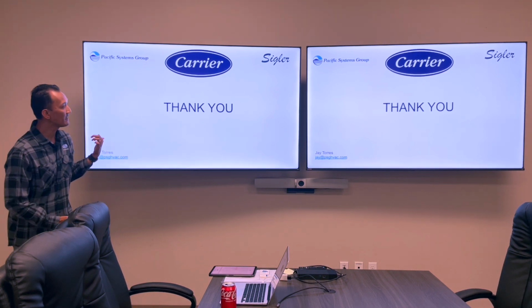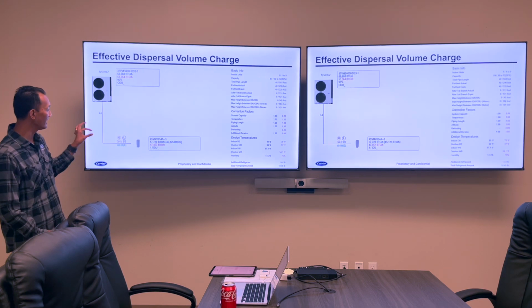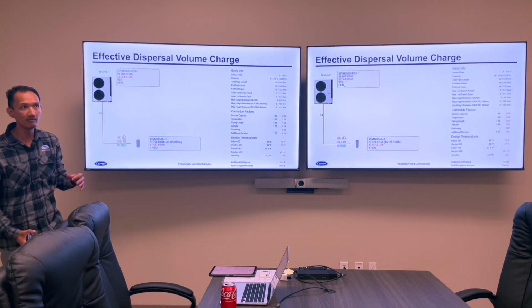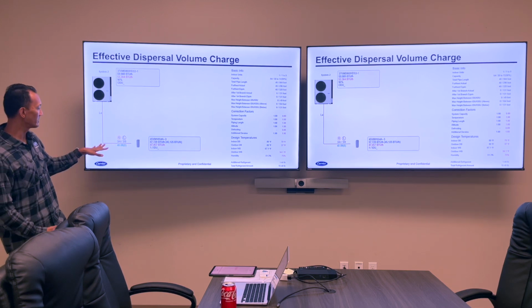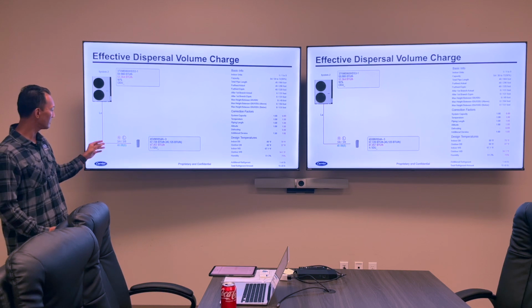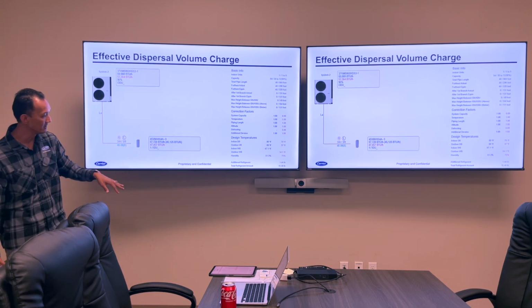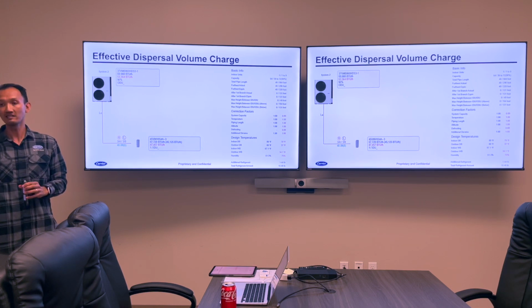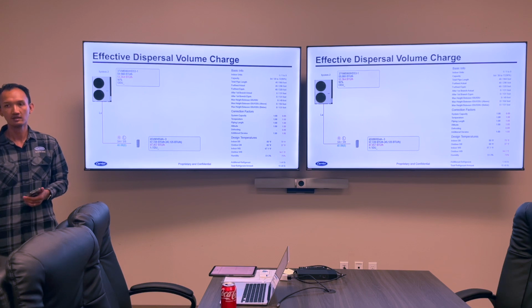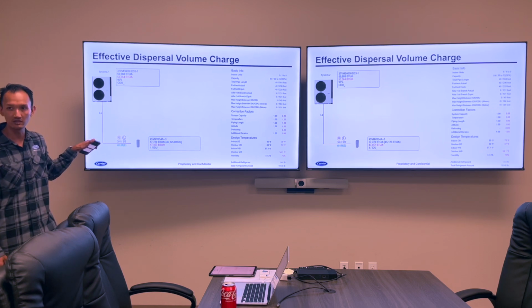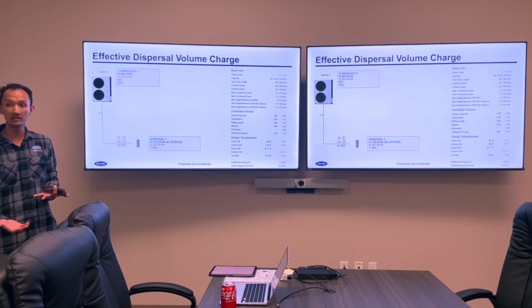Yeah. So if that were the case, we would go back and see that we wouldn't comply, and then we would place an SV box. Depending on the building, we can figure out where it needs to sit between the outdoor and the indoor units, and then our software, depending on where it sits, would calculate. Say it's 25 feet from the box to the fan coil. The software will tell us how much refrigerant would potentially leak with this SV box in place, and then we can figure out if it's less than 22.2 pounds. If it doesn't comply, we would go back and put the SV box where it needs to go, then calculate the releasable charge and figure out if it complies or not. Based on the length of the line.